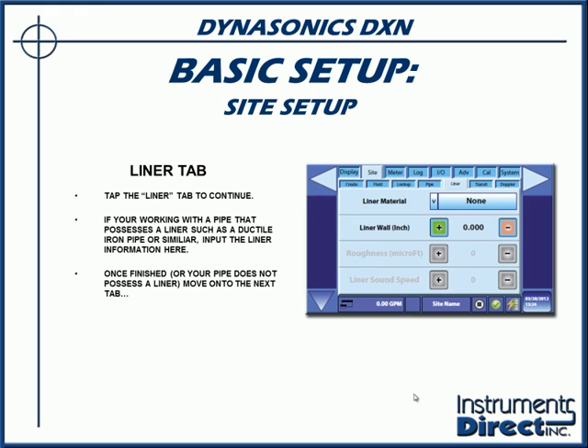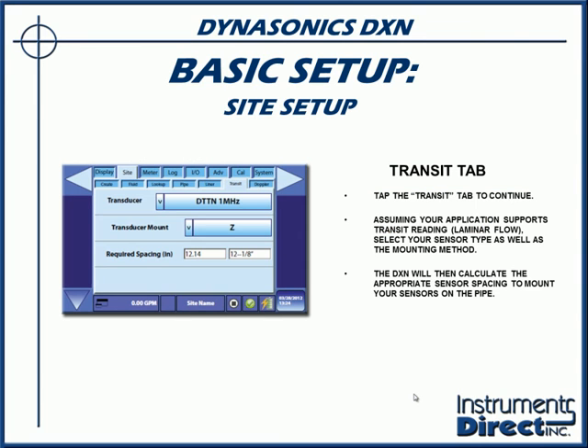Should you have a unique application like a ductile iron pipe with a liner on the inside of the pipe, again, this would be the point to put the liner information. You can drop in the various choices of mortar linings and so on, again, from the drop-down bar. So if we're using an ultrasonic transit time flow meter, then we will select the type of transducer based upon your pipe size. We showed you a chart a little bit before there on the drop-down.